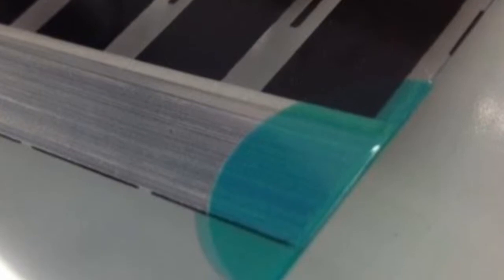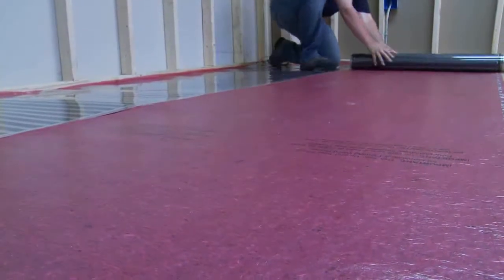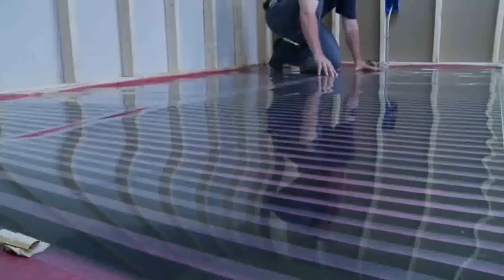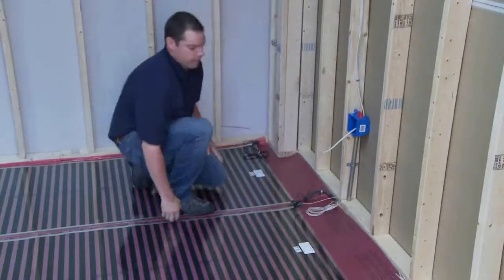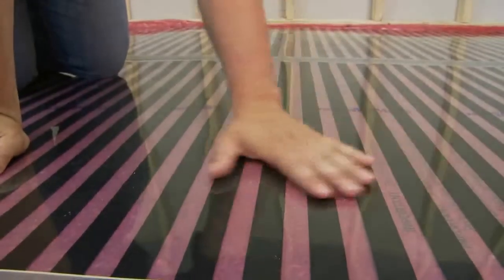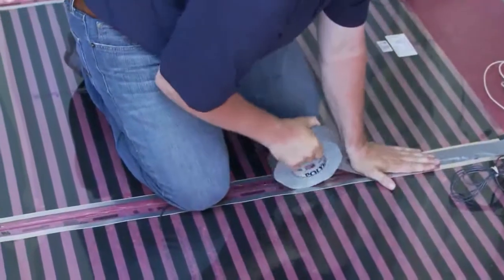Insulate the cut ends of the bus bars opposite the connectors with Kapton discs. The Perfectly Warm floating floor heat film can be positioned in place and simply rolled out to provide maximum floor coverage according to your design layout. Leave a minimum 2-inch gap from the wall. The installed heating panel surface should be smooth and free from any ripples or creases. Firmly attach the heating elements to the floor.